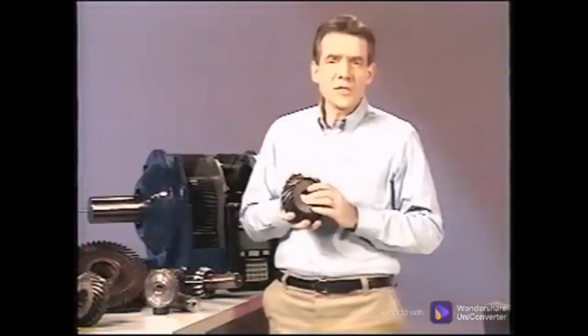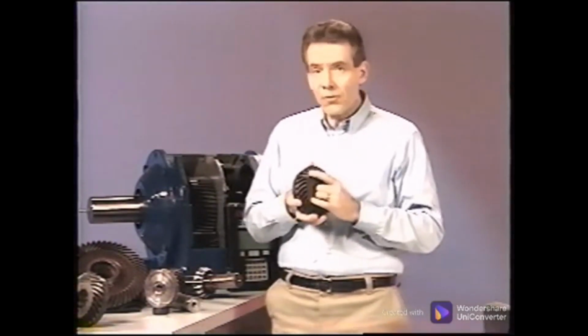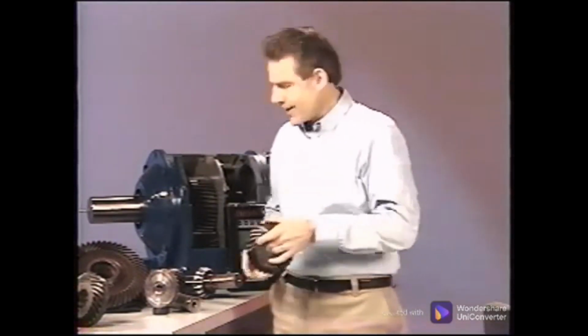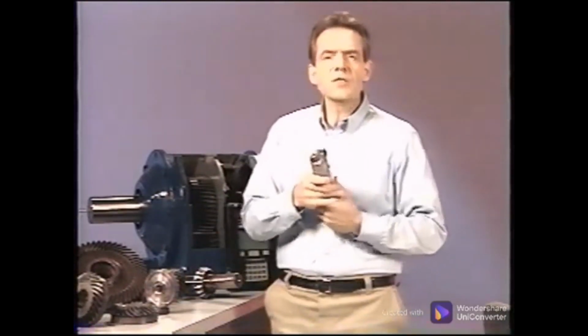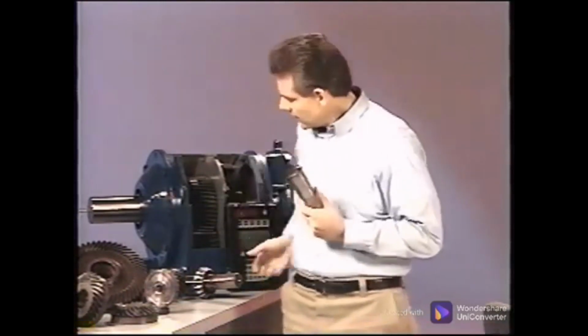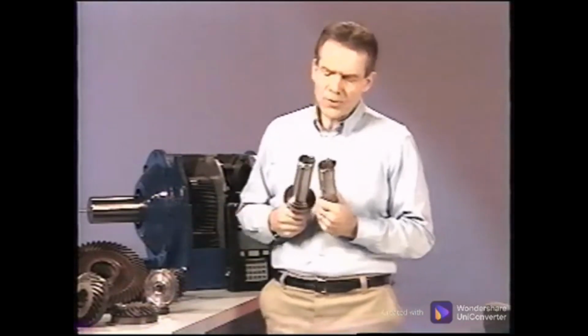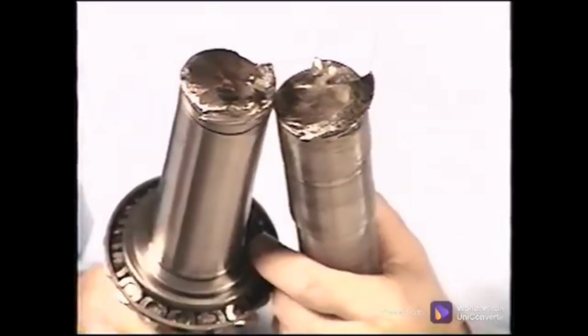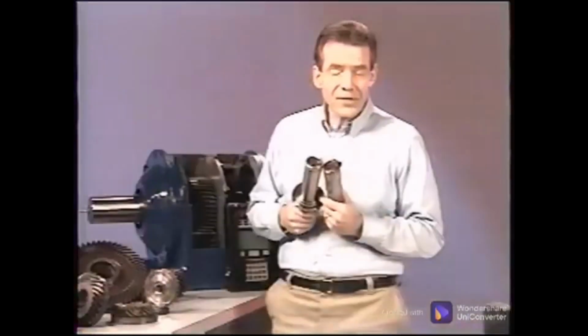Gears can take an enormous amount of torque, and usually without damage. However, sometimes the metal does fatigue, or the force is so strong, teeth chip or break. This shaft was at a right-angle gearbox, similar to one these gears came from. When an excessive amount of torque was placed on the driven unit, this shaft twisted in two, but the gears were not damaged. When a tooth breaks, there is a pulse that impacts once each revolution.